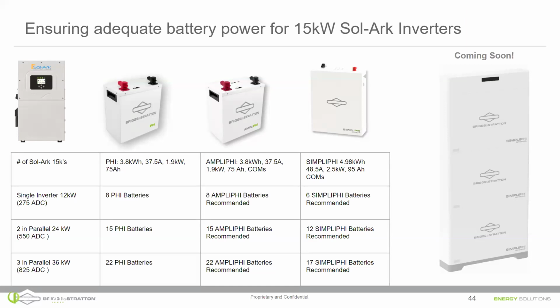Anytime you have an inverter and a battery bank, you want to make sure you have enough battery kilowatt hours, or fuel in the tank, to support the home loads during time of use or during backup. But you also need a battery bank large enough to provide enough power, enough watts, enough ability to discharge quickly to support an inverter that's being called upon to back up a lot of the home.